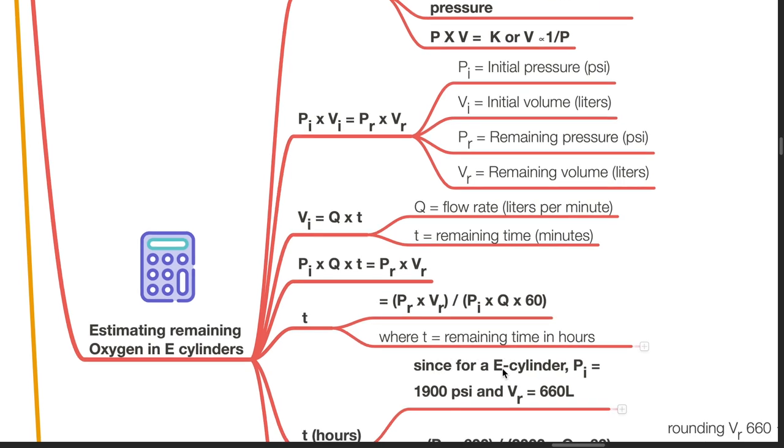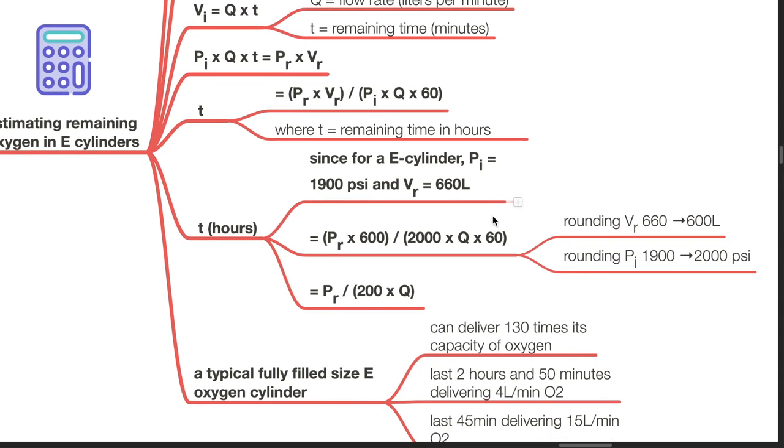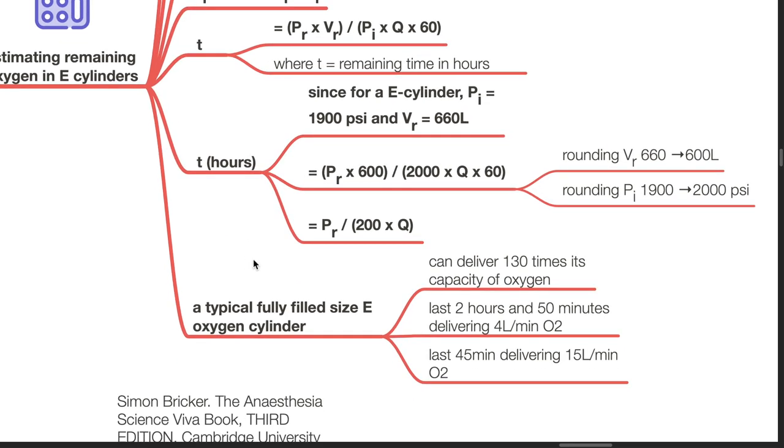where T is remaining time in hours. Since for an E-cylinder, PI equals 1,900 PSI and VR equals 660 litres, PR times 600 divided by 2000 times Q times 60, rounding VR of 660 to 600 litres and rounding PI to 2000 PSI, PR divided by 200 times Q equals T in hours. A typically fully filled size E oxygen cylinder can deliver 130 times its capacity of oxygen, last 2 hours and 50 minutes delivering 4 litres per minute of oxygen, and last 45 minutes delivering 15 litres per minute of oxygen.